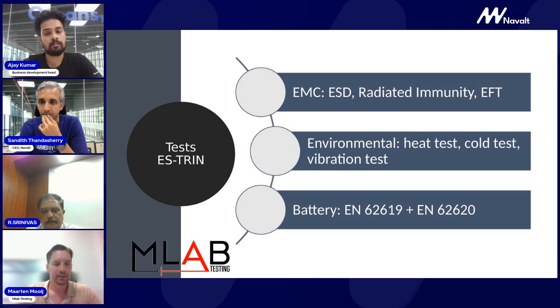With the ESD test, we have a small gun, and you apply a few kilovolts on your product, like you're charged, or there's another product being charged for whichever reason, and you will discharge your energy basically to the product, and your product has to remain safe about this. And this voltage can go up to a few kilovolts.